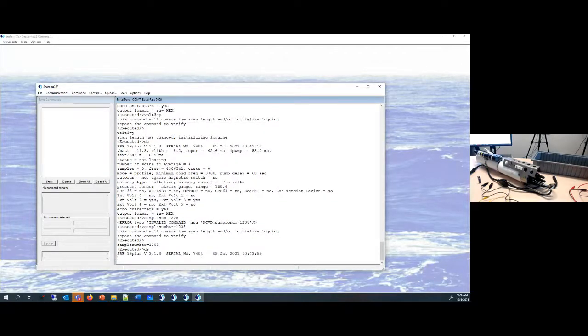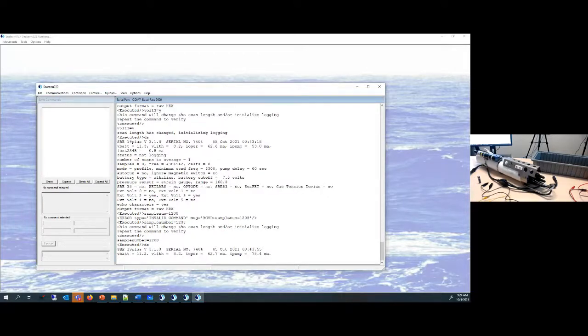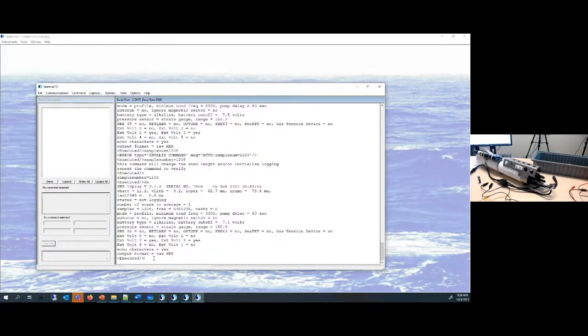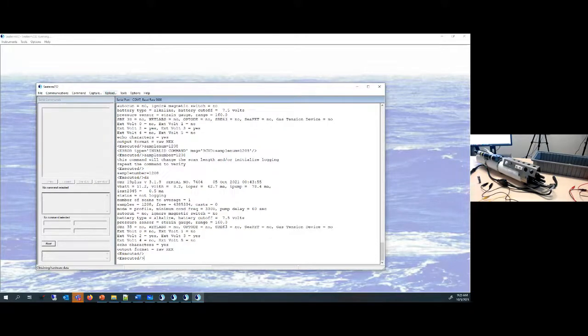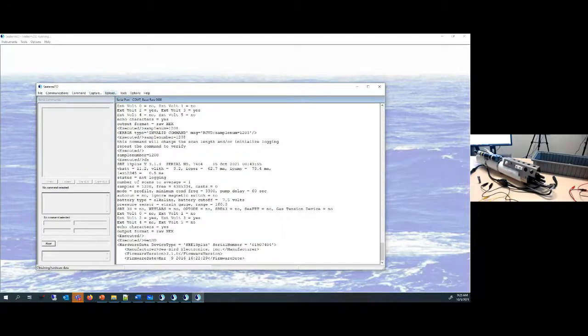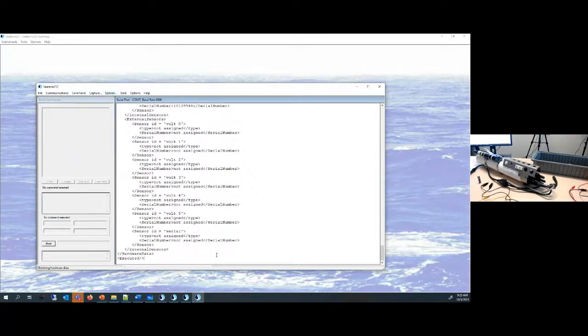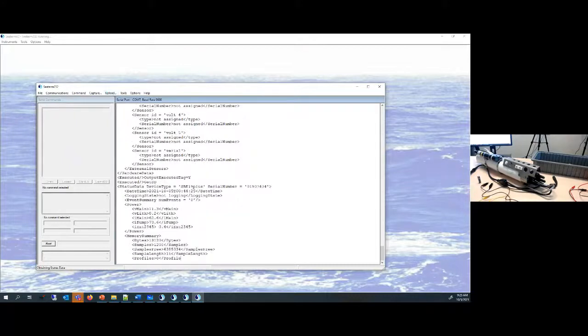And now when I send the DS command, I see that it says it has 1208 samples in the memory. Essentially, by initializing logging in the first place, we rewound the tape back to the beginning. And by setting the sample number to 1208, we fast forwarded it back to that spot. From this point, we can go ahead and upload our data again. And it's going to hopefully upload data from the CTD up to the point of sample number 1208.